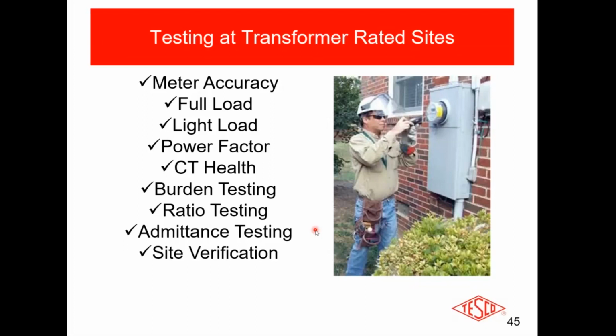You didn't get additional corrosion. The connection didn't loosen up on you, because any of those things that occurred would have started to change your admittance test. So an admittance test is even better than a picture because it tells you if anything changed in the circuit, including things that might not be readily apparent. And then you do a site verification, which is checking everything else about it. The wires, the connections, make sure nothing is broken, make sure nothing's loose, make sure that there's no live animals in there. That's always exciting when you open up a box and there's a live animal in there.